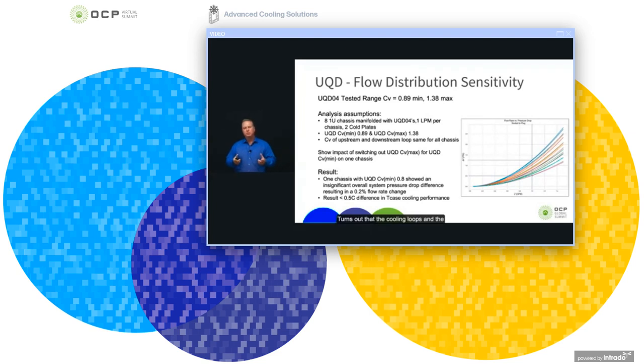Turns out that the cooling loops and the cold plates, the delta P's across those components are orders of magnitude higher than what you find with the UQD. So the impact of the UQD on the system when interchanged is very minimal. And when we look at it from a performance standpoint, switching them out as I've described, we see a temperature difference at the processor of less than half a degree. So very minimal impact to having a wide range of UQDs because of the very low delta P across the QD relative to the other components in the system.